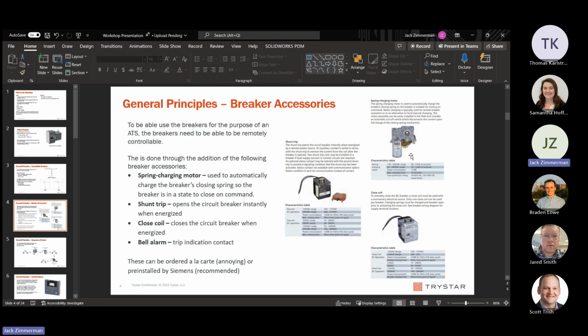They're relatively necessary together, because if you want an automatic transfer switch and your coil's not charged, your controller is going to try to close the breaker, but it's not going to work because you have no energy stored within that breaker to actually activate it. Isn't the spring coil what would be used with just a manual handle normally? You basically pump that up and that's what you are able to close that breaker with.